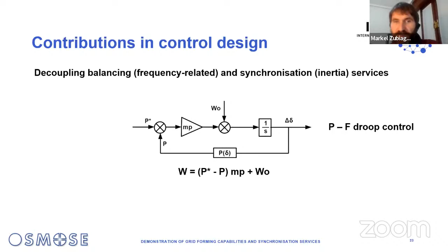So we added a filtering or feedback from the internal frequency to the set point. This way we can call it transient grid forming, or transient P-f droop control. If a change happens in the angle or the frequency, this still reacts the same way as the P-f does. But if the frequency change is extended in time, the filtering prevents this control from continuing to act. So in short, this avoids the frequency control by decoupling it, while it still keeps the synchronization service. Of course, it's not for free — the inertia constant is affected by the filtering constant, so both have to be in accordance.